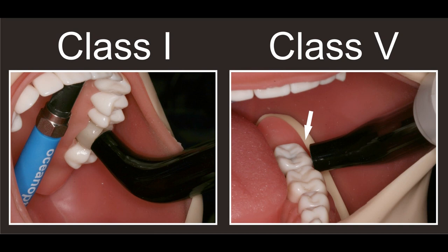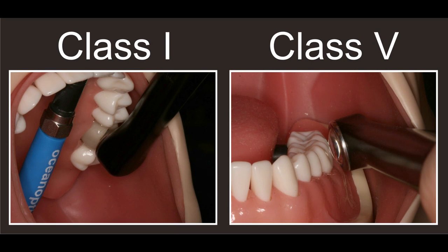Here we can see an example of a curing light with a light guide. Note how difficult it is to get into the Class I and Class V locations. This shows how relatively easy it was to get another curing light into those same locations. Even so, the 20 operators using this particular curing light for the same amount of curing time delivered between 4.4 and 17.4 joules per centimeter squared.